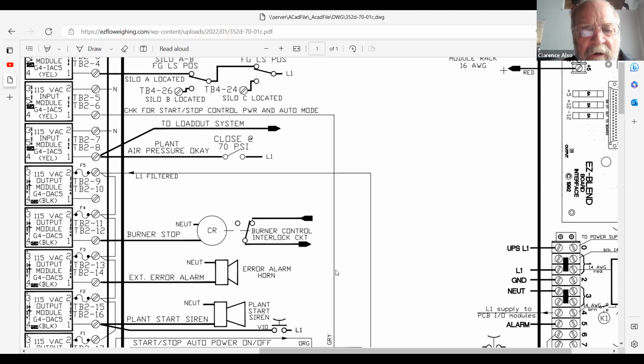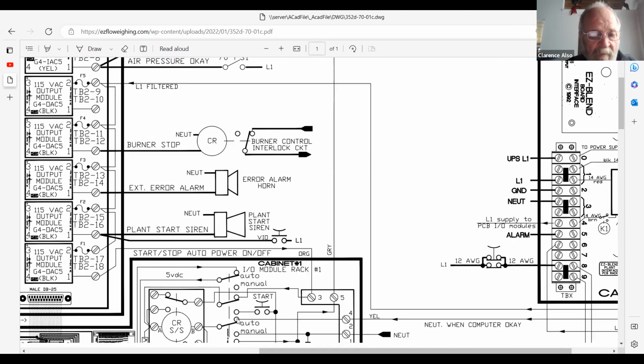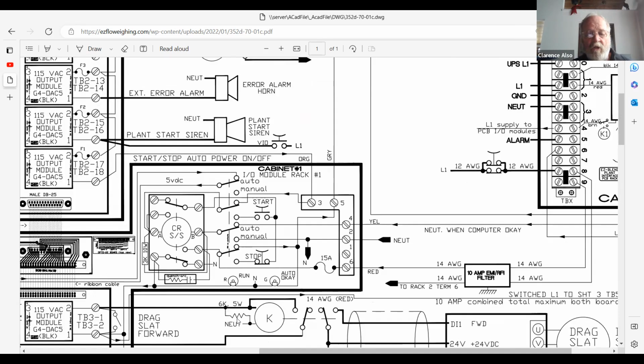And that shows a single pole double throw. That means there's one pole and then you either can go in one direction or the other. And right now it says, okay, I am normally closed. That's a normally closed set of contacts. And then when you energize that, it's going to open it up and it will open up the burner control circuit. That's what that one's for. You got some outputs below the black one. The horn's supposed to go out for error. There's another siren also. If your siren's not working, well, maybe automatically, that's where you maybe go take a look at. These are the kind of things that, by looking at your drawings, brings you up to speed on stuff. And you know where to do some troubleshooting much quicker.